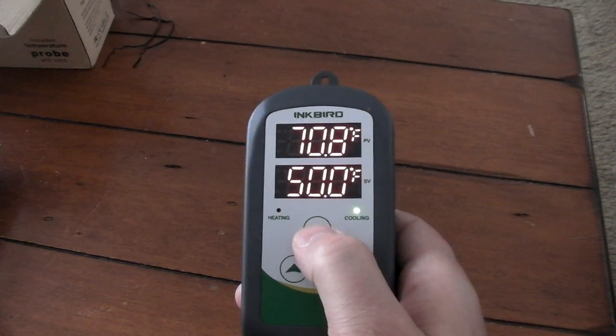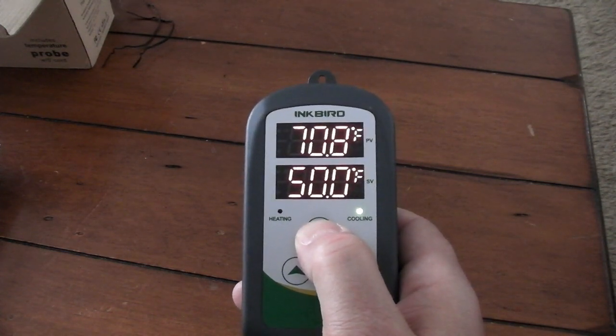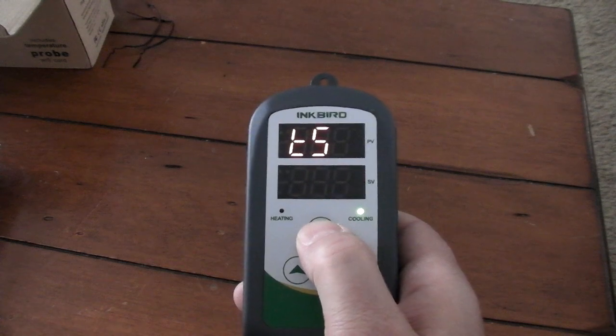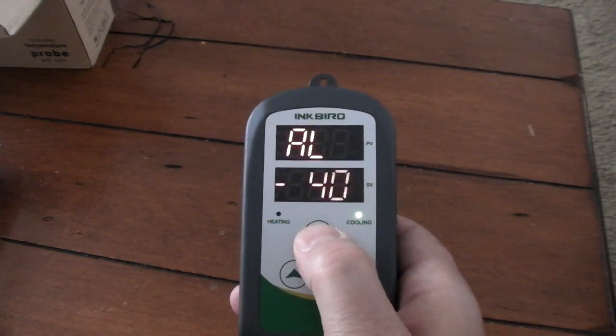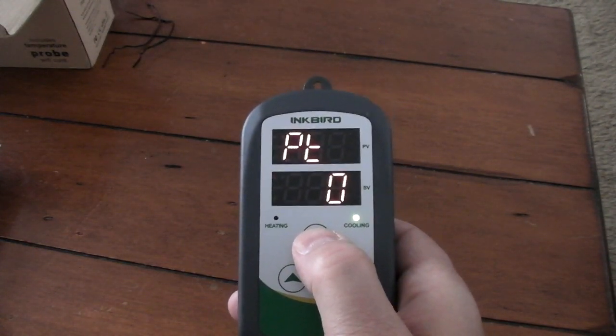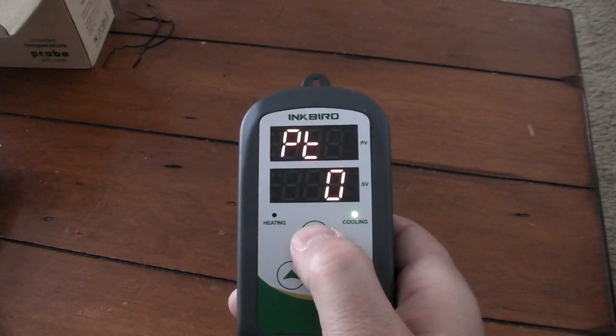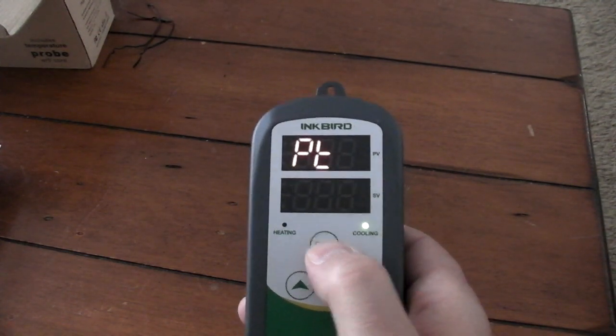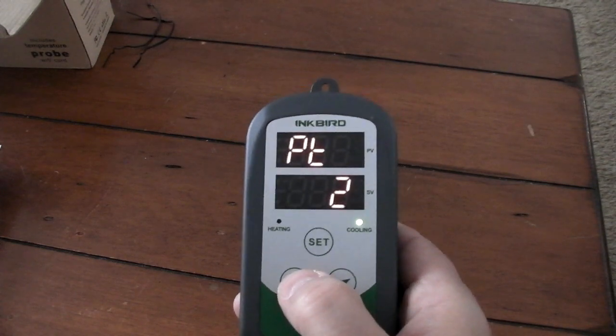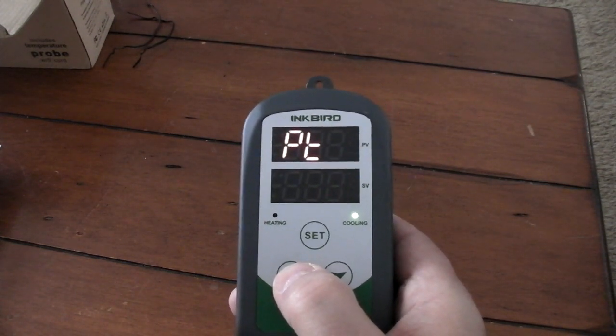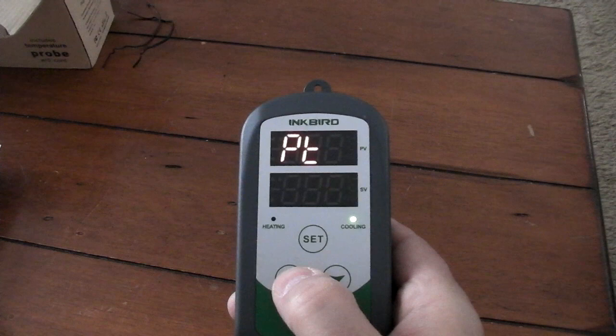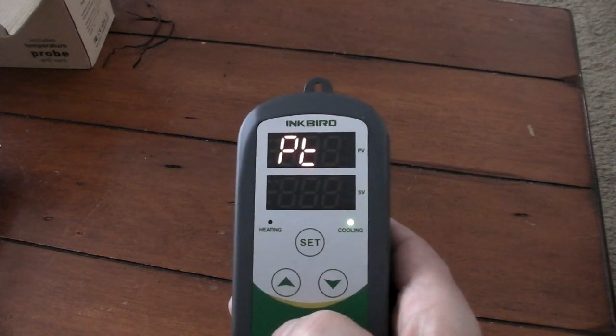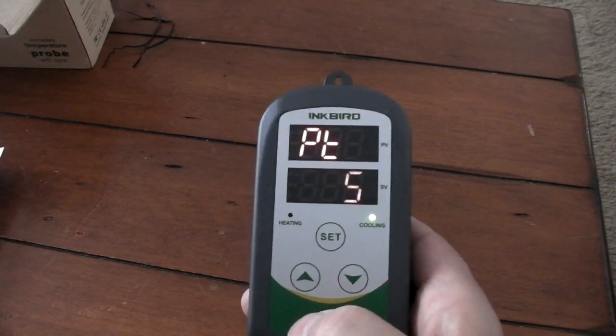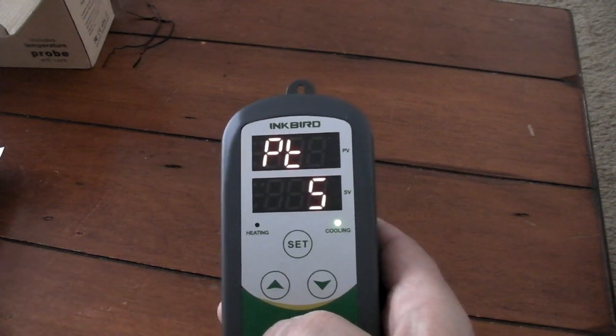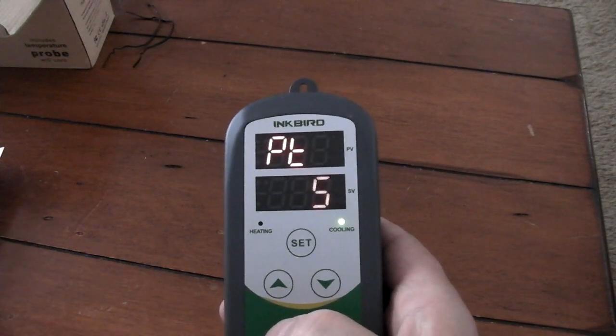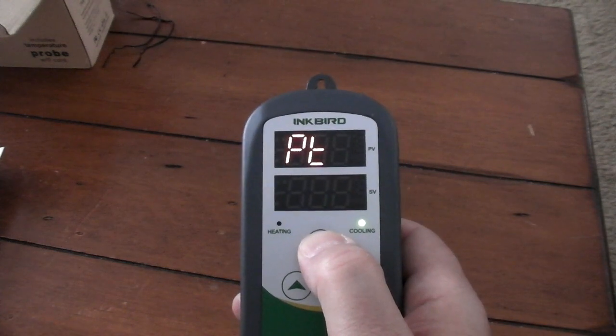And then there's also a, let's see, press and hold this. If you go through, PT is compressor delay. Let's do the compressor delay. This is in minutes, and you can go up to 10-minute delay. So I'm going to go 5-minute delay in between cyclings. So it'll take 5 minutes out, let the compressor rest before it turns on again, then press set.